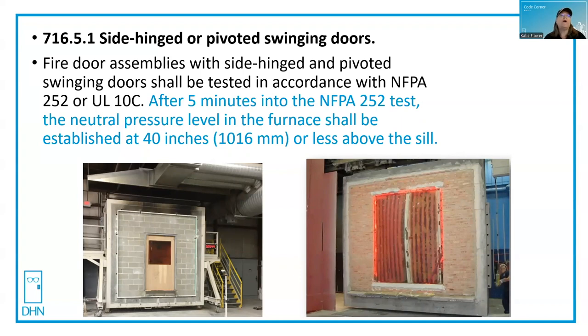The part in blue states that after five minutes into the NFPA 252 test, the neutral pressure level in the furnace shall be established at 40 inches or less above the sill. This is because the NFPA 252 test could be either neutral or positive pressure. The architect would have to specify, and you would look in your wood and metal door specifications just to confirm that yes, it should be UL 10C.